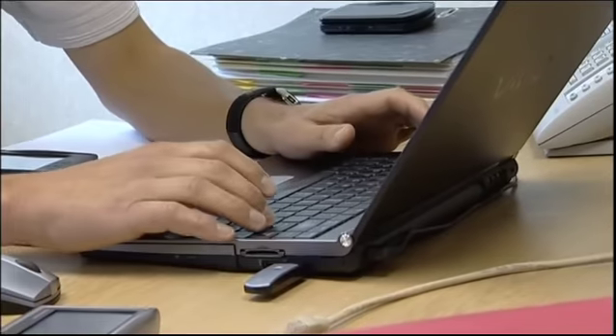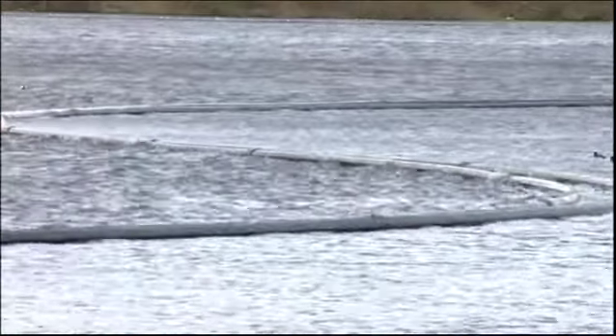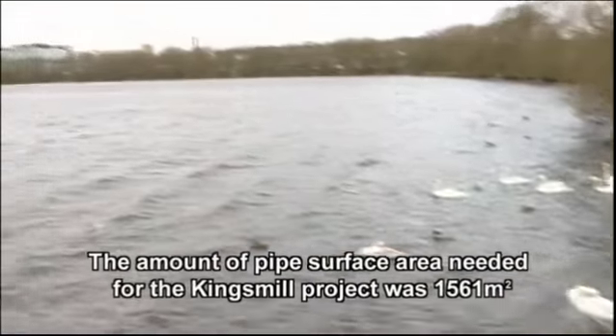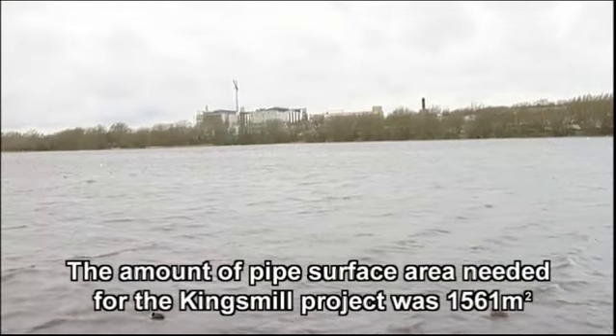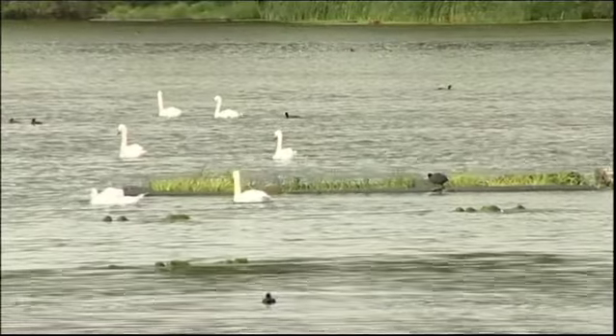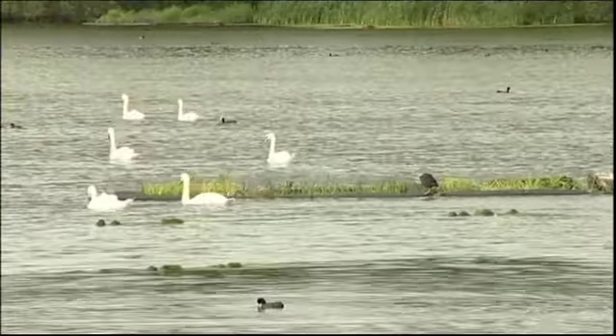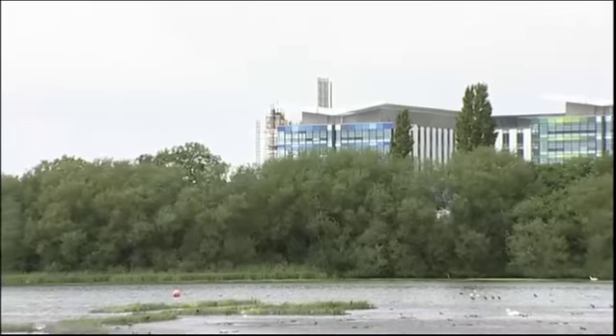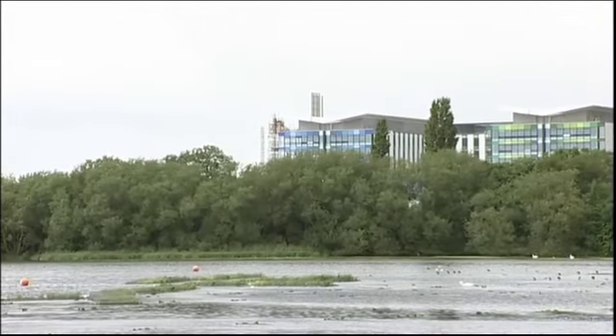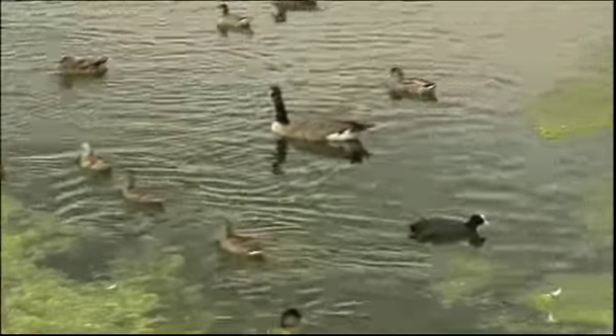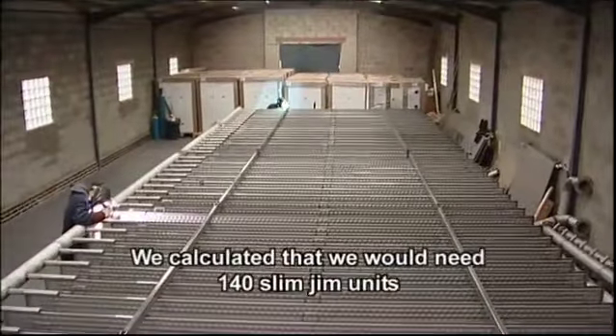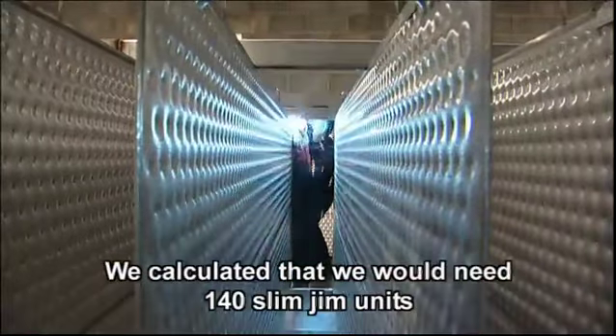Special software was used to calculate the amount of slim jim heat exchanger surface area needed to provide the hospital's required heating and cooling loads in the water mass available in the reservoir. For the Kingsmill project, this was 1,561 square metres. The software also calculated the resulting temperature changes in the water to make sure there'll be no adverse environmental impact on the reservoir. In this case, it actually produced a small benefit to the ecology of the reservoir. For Kingsmill Hospital, this calculation showed that we would need 140 slim jim units.